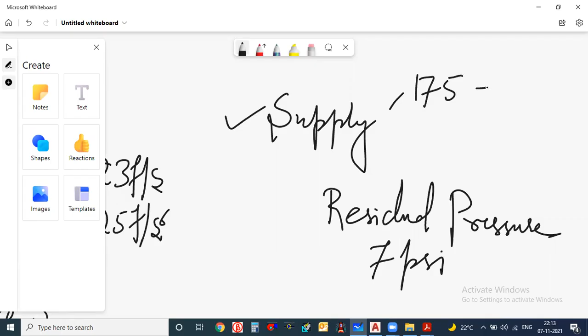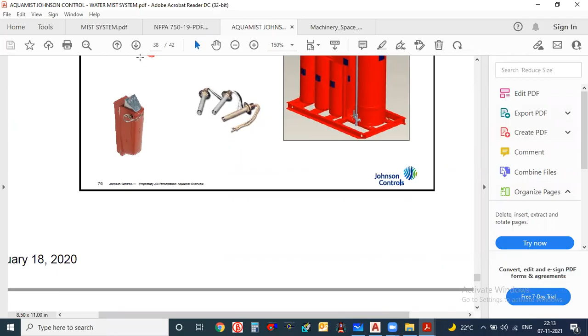And the next thing we can do is change this value to 25 feet per second. So these two changes you can do. Rest everything, like pipe: if you want to select copper pipe, you can select the copper pipe, whatever code number is given. The C factor will automatically update. The K factor also you can select, based on this document, where they have given the K factor somewhere. That value can be selected. Rest everything, equivalent pipe type, equivalent pipe length and all, will automatically update. So the rest everything remains the same only.